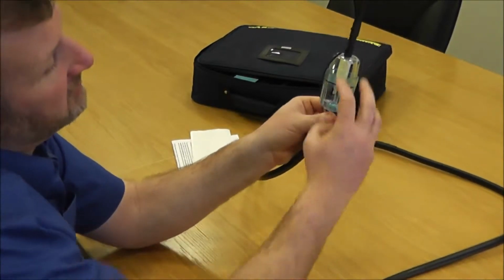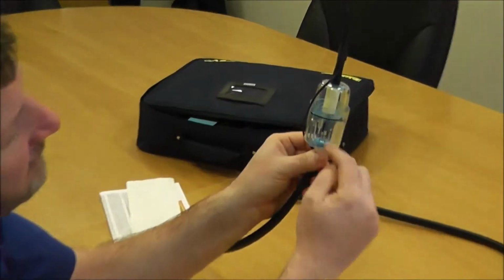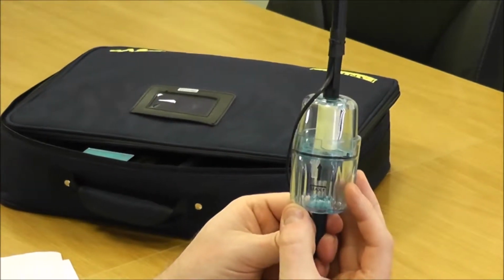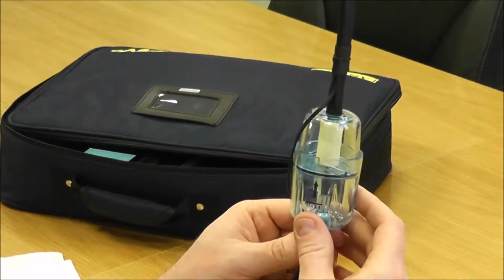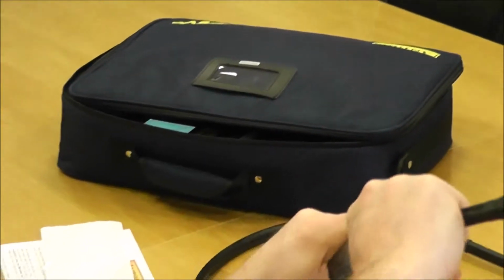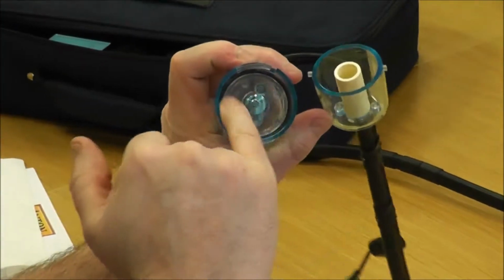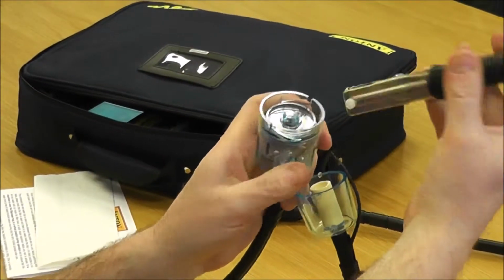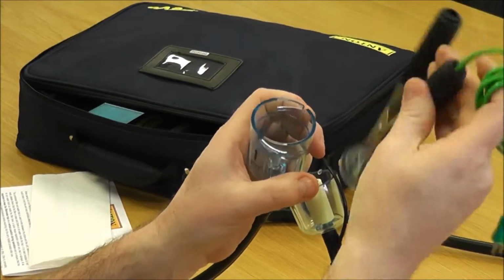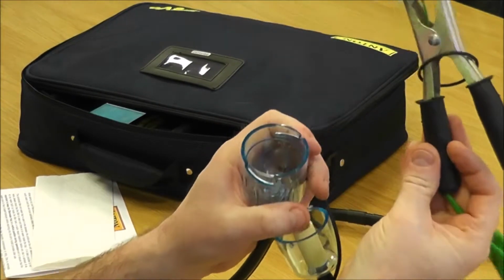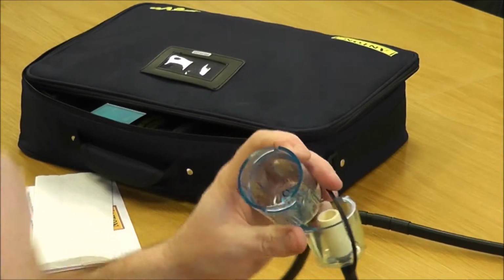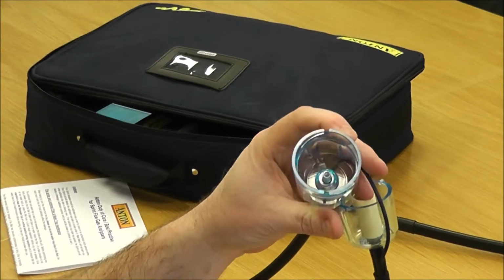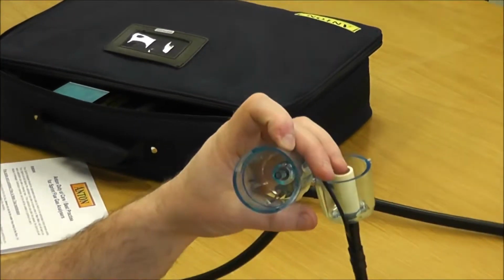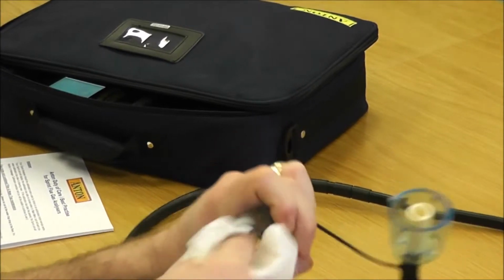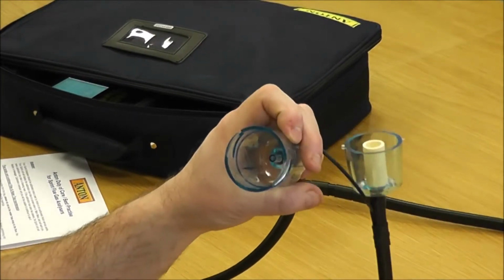If you did have water in, this is a split chamber filter bowl. So what you've got on the bottom is for capturing the moisture, and on the top is for capturing the particulates. Inside there, you've got two compartments separated by a middle disc. Now that middle disc can be removed. If you use a clamp probe, it's quite handy because it helps you to remove it if you've got no nails like me, and also it captures the O-ring so you can't lose the O-ring. Now obviously what you do is, when you open that up, if there was any moisture, any condensate at all, it needs to come out, and you just dry it out. So you get a dry cloth, go inside there, and once you remove the middle disc, it allows you plenty of room to take all the moisture out.